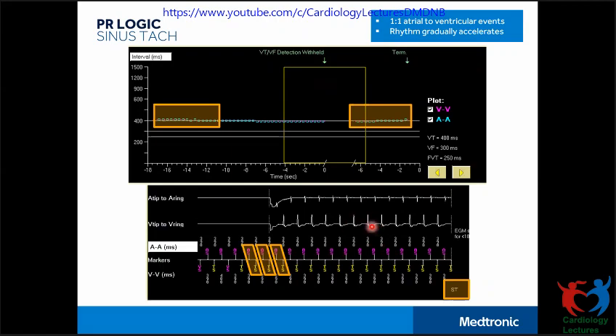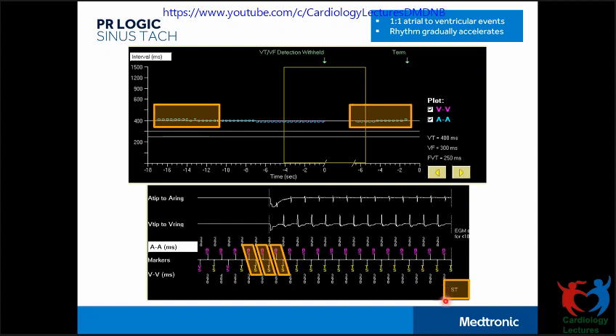Third is the sinus tachycardia feature. This feature identifies sinus tachycardia and withholds detection when there is a 1:1 atrial-to-ventricular conduction that exhibits a gradual increase in rate into the detection zone, and a PR interval similar to that of normal antegrade conduction. In this example, the plot shows 1:1 conduction gradually going into the VT zone, and the PR interval either gradually changes or remains stable.